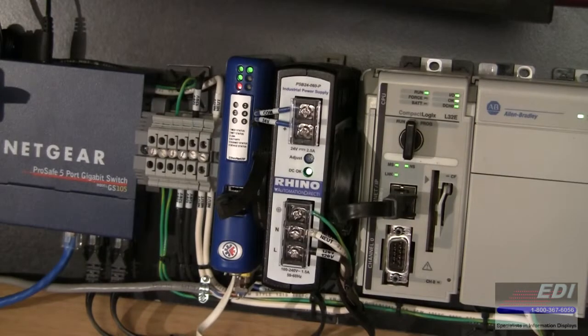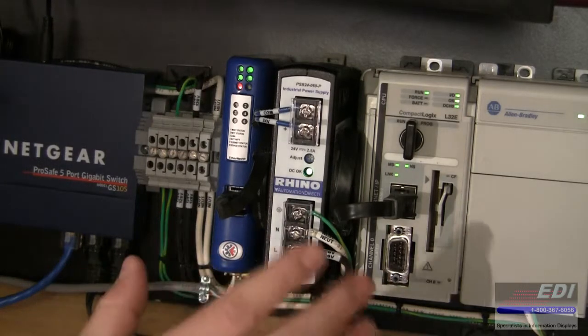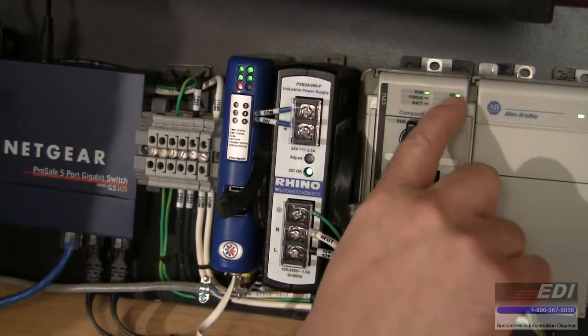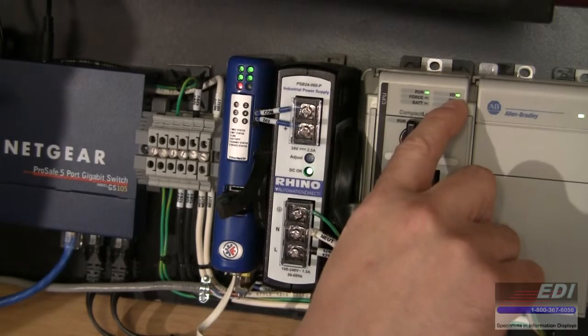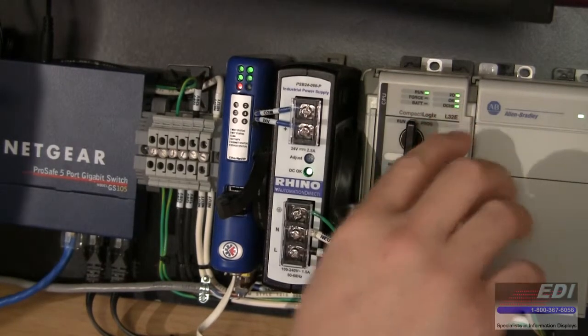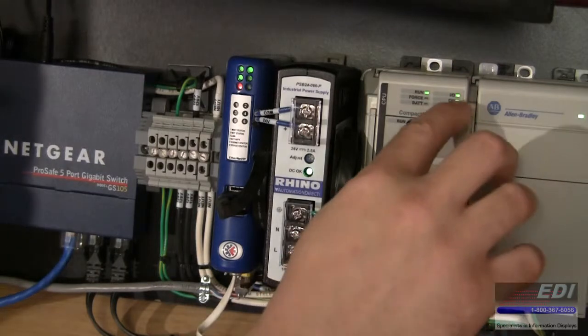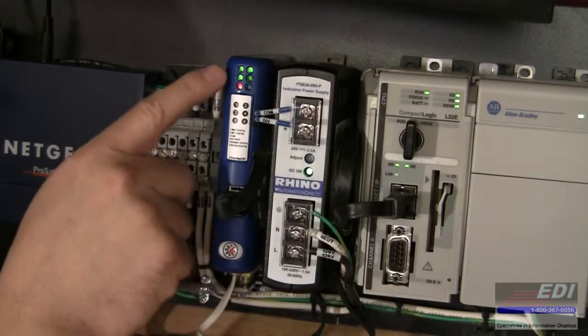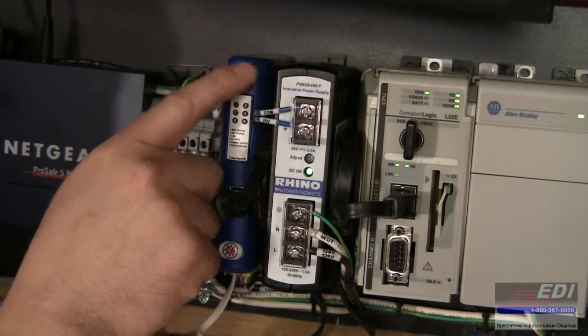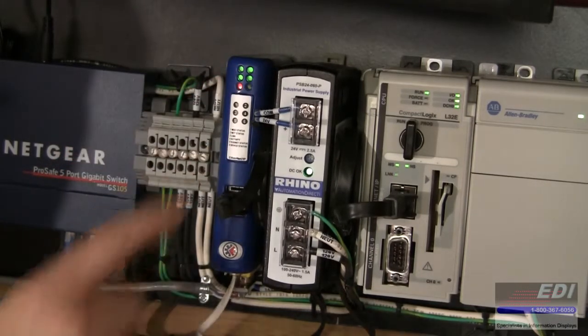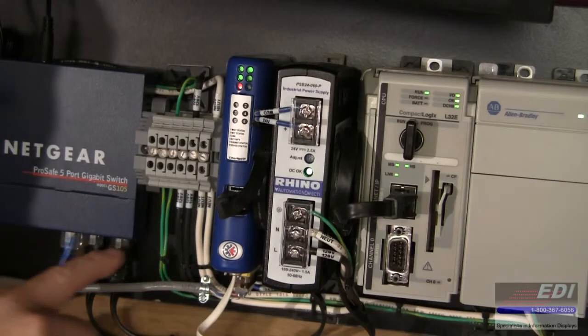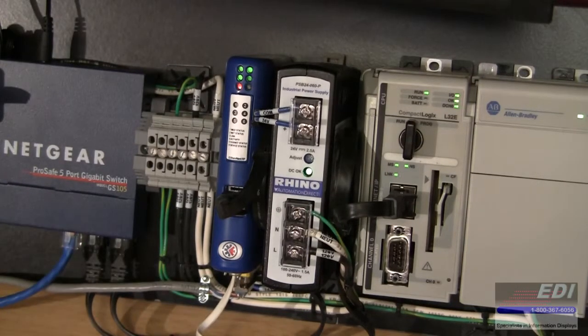Let's go over to the camera view now. There's a couple things to confirm here. One is that we don't have a blinking IO light on the PLC. If it's blinking that means we've done something inappropriate or something's wrong. Then let's confirm that we have steady lights across the two top parts of the AnyBus Communicator as well as activity lights on our network switch.